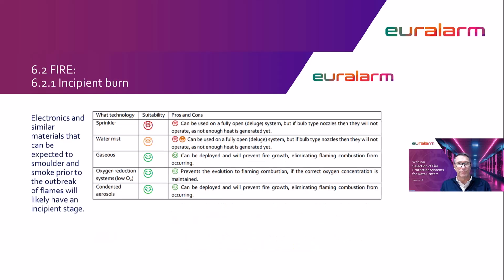Next step, the first in fire, an incipient fire. Think a component failure in the white space. There's no heat, so sprinklers can't operate. Deluge water mist could, if detector triggered, but that has wide-reaching consequences. A gas system could prevent this escalating to flaming fire, so far better, and an oxygen reduction system would prevent it, presuming you're at the right residual oxygen level.